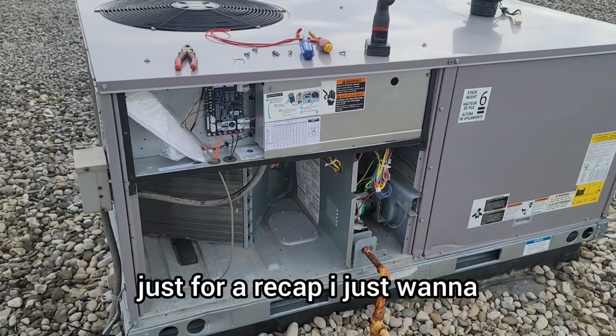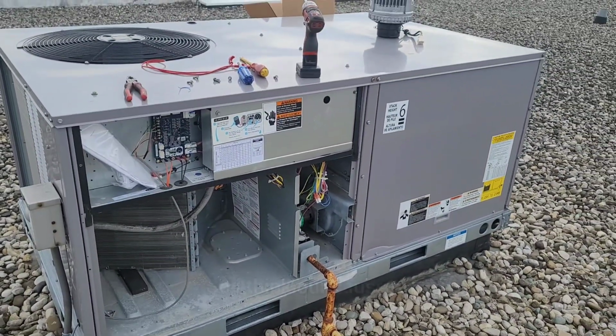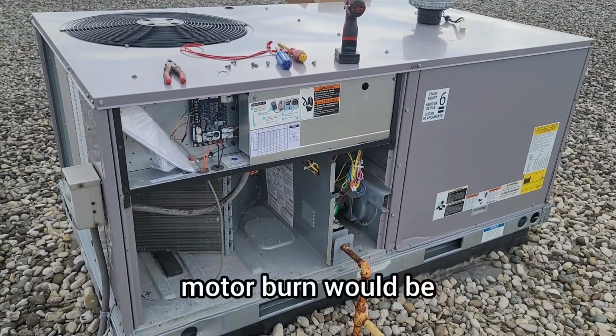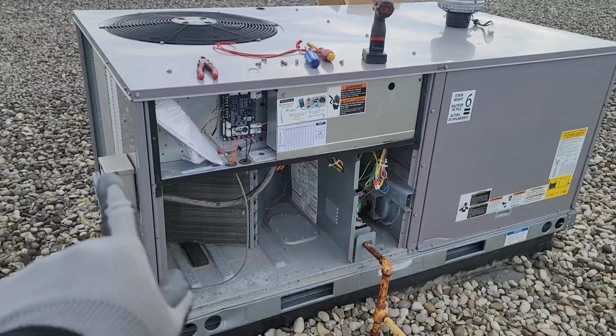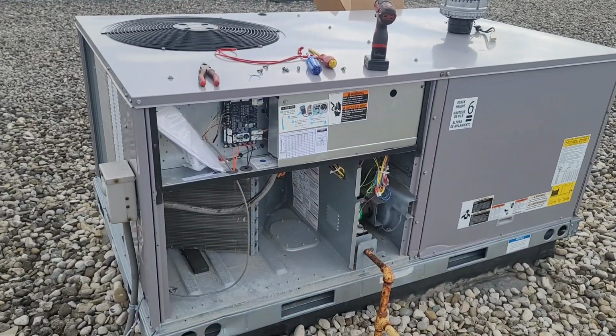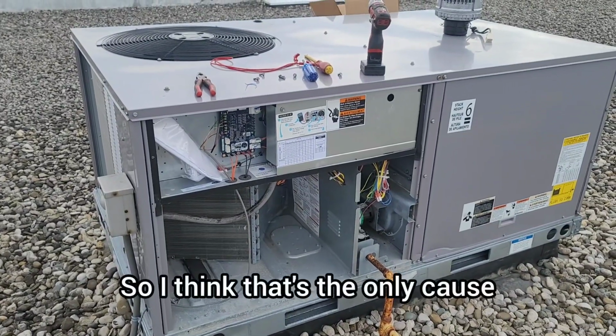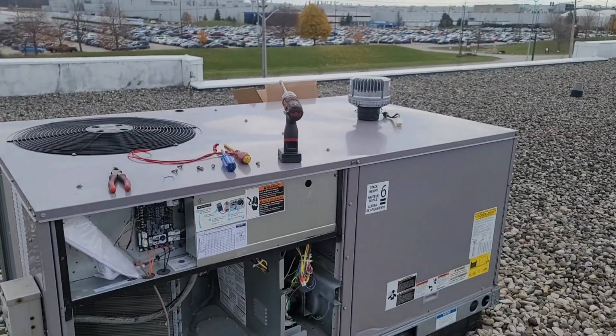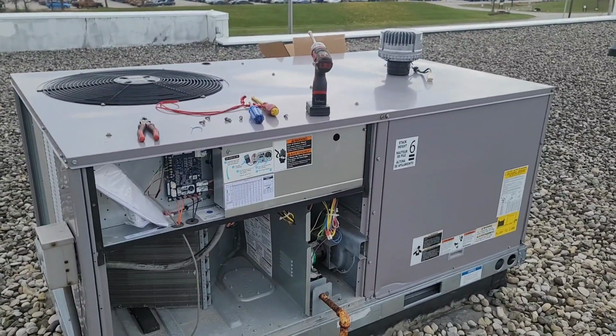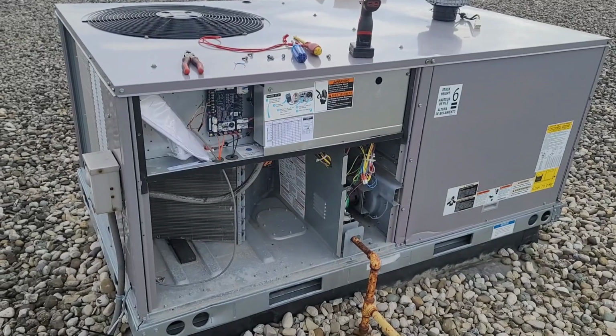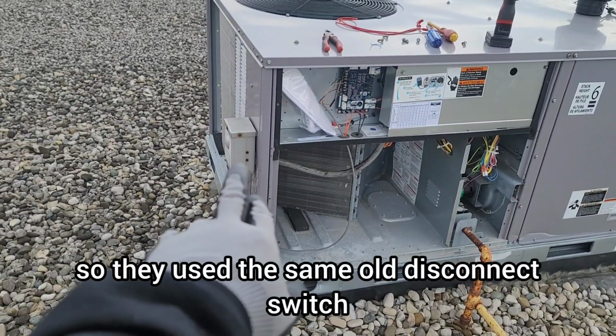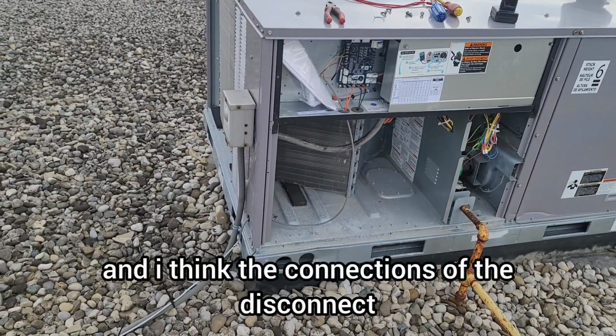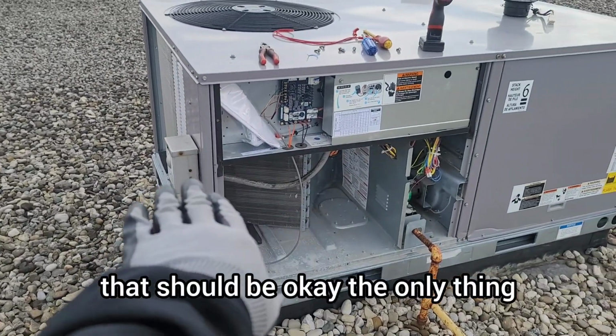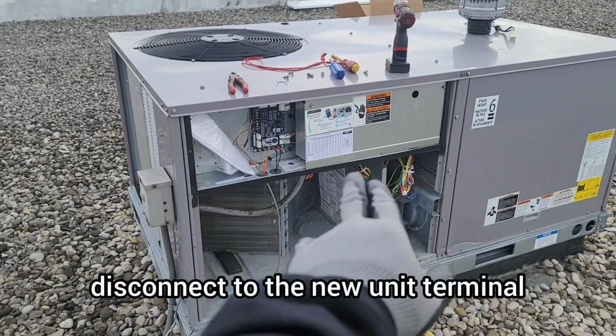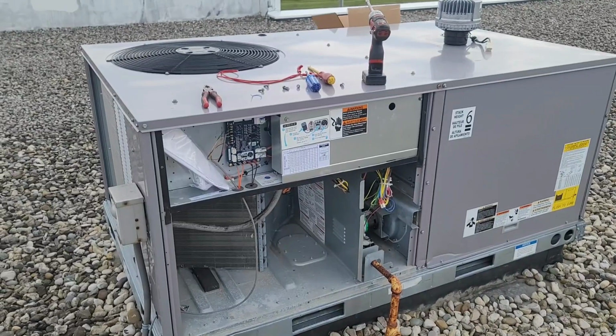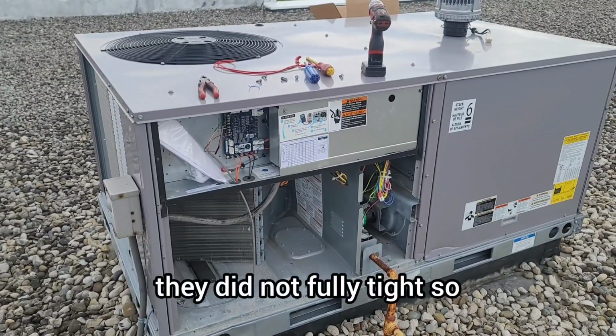Just for a recap, I think the cause of the motor burn would be the loose wire I found, which was going from one of the three-phase power supply lines to the terminal block, and I found it loose. I think that's the only cause, because these motors are very good quality and they rarely go bad, and that was very expensive. So they used the same old disconnect switch from the previous unit, and I think the connections of the disconnect, they haven't touched, should be okay. The only thing is, when they connected the power supply from the disconnect to the new unit terminal, they did not fully tighten it.